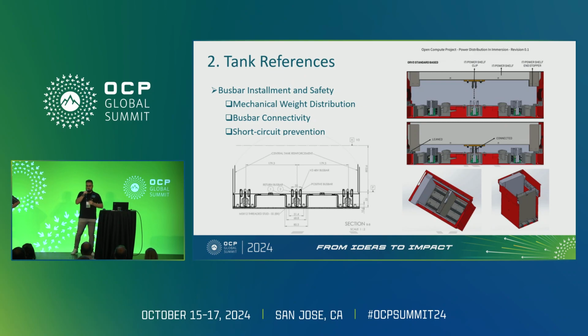Then there is the short circuit prevention. The design of the ORV3 busbar compared to the Open Rack version 2 busbar is way better. You need to think that in a tank, gravity goes downside, so if we drop something into it, it may fall onto the busbar and cause a short circuit. But this is prevented because of its new design, where the positive and negative are completely different than before.